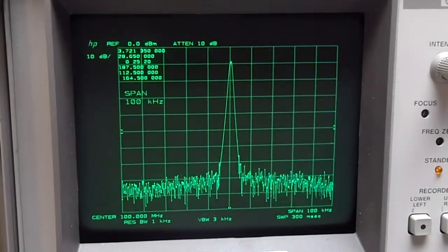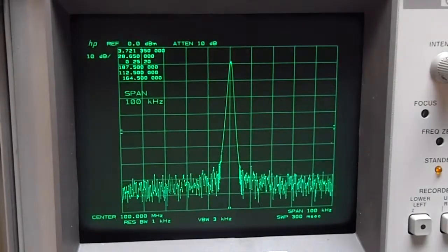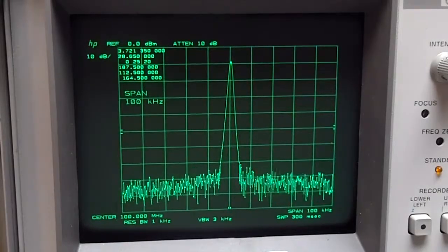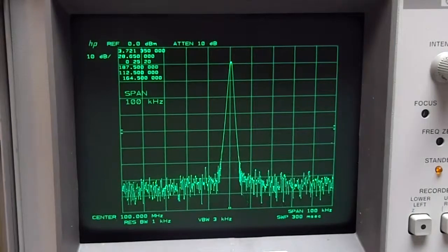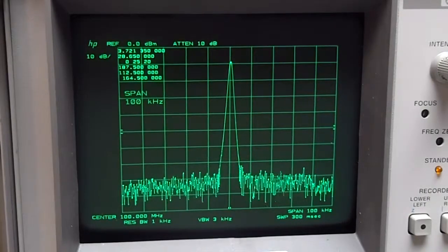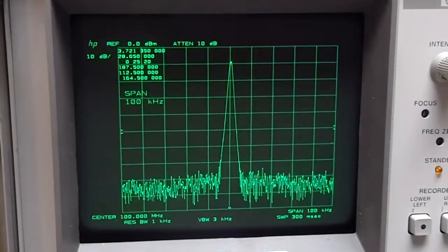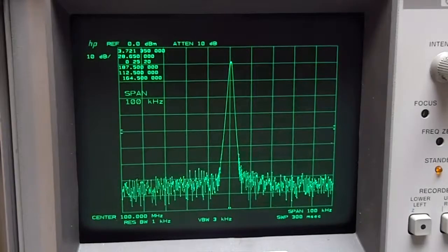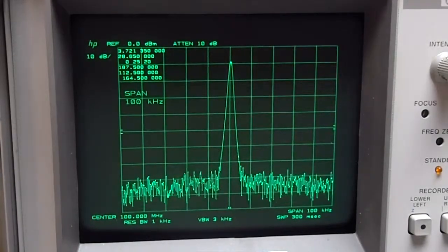And you can go to your first LO output and monitor that with a frequency counter or another spectrum analyzer and put the instrument in 0 span, and so it's only going to put out that very first frequency that you see there, and it should be exactly that frequency plus or minus the error of your reference oscillators. You can lock them and then you won't have any. And also, if you're using it in 0 span, you might want to shut off your sweep.